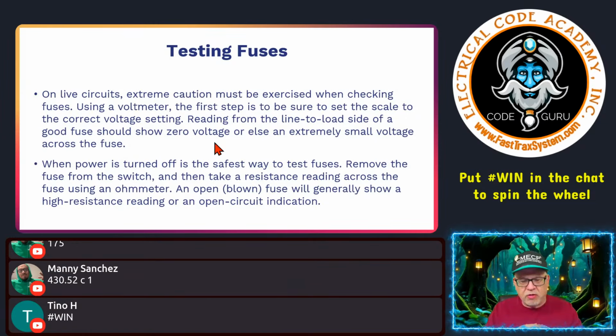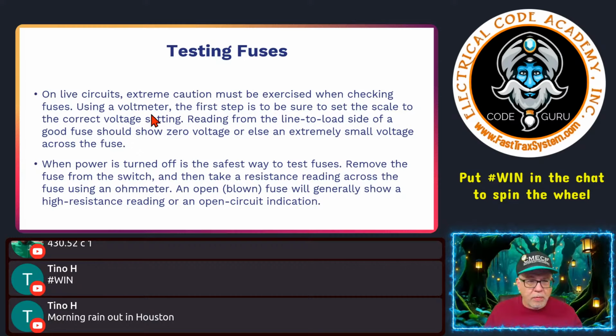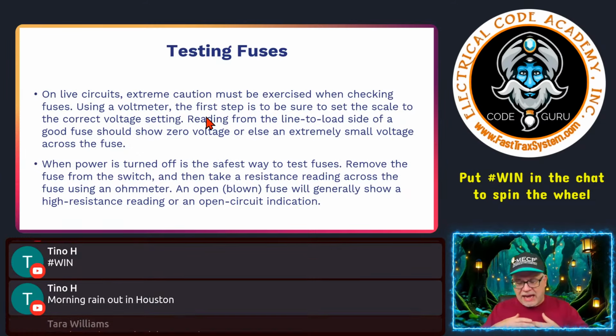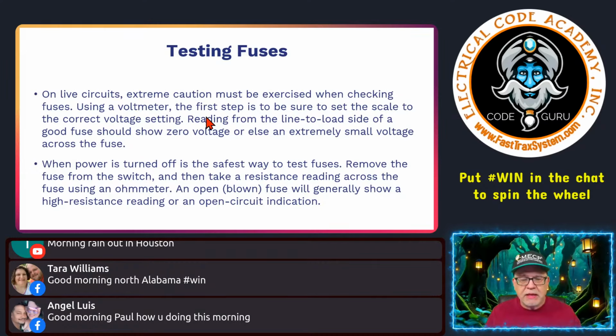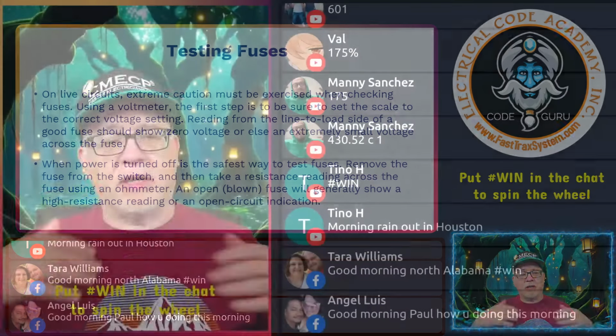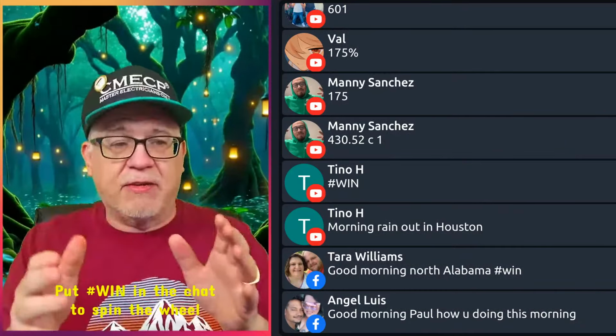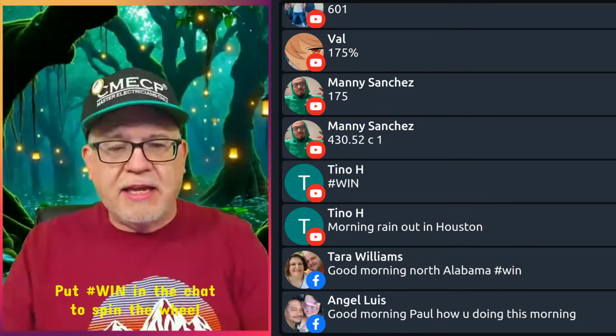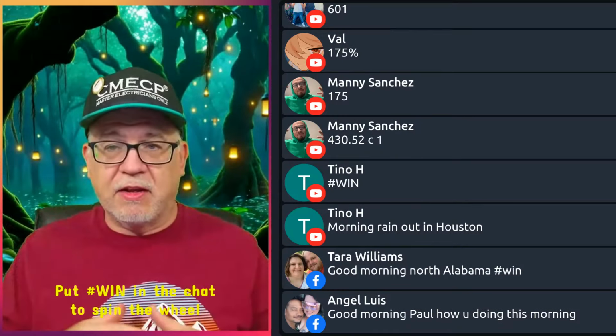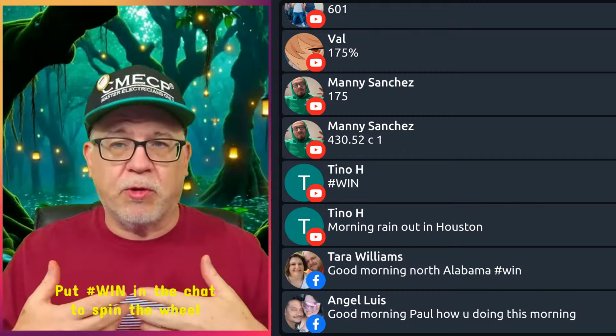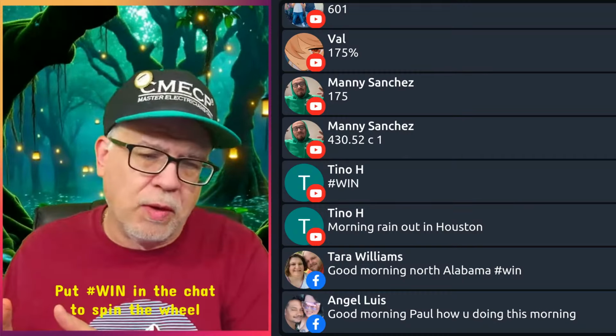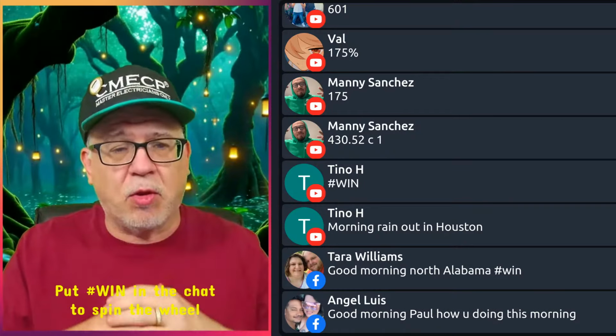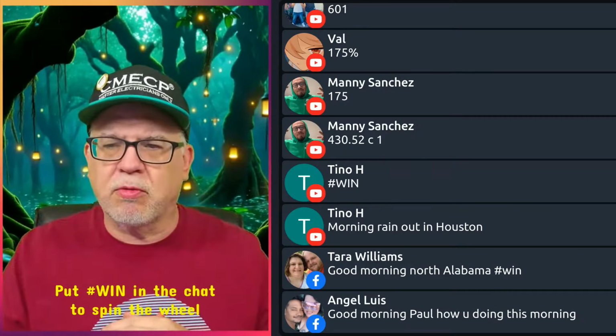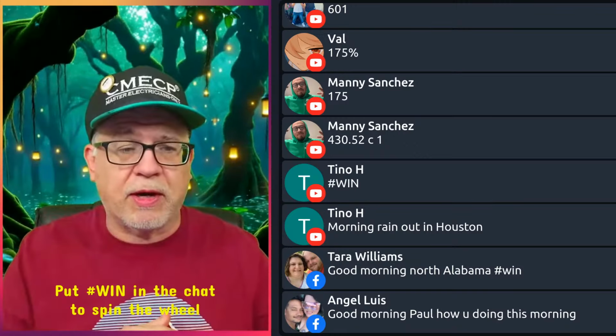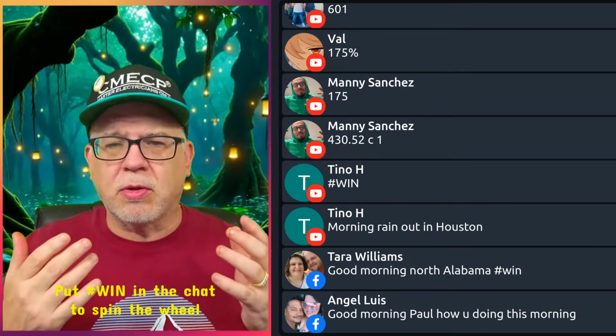Now, when power is turned off is the safest way to test. Now, this is another thing right here. People ask, for example, about working clearances at disconnects for HVAC equipment. I get this question all the time. They ask me, do I need working clearance at an outdoor HVAC equipment disconnect for the condenser? And the answer to that is yes. It has to have working clearance because chances are that is the place that you're going to be going if you're a technician checking before you start digging into the equipment. You're going to be right there making sure that you have the line voltage, that the fuses are okay, that everything's passing through fine, that you've got the right level of voltage, you didn't lose a leg anywhere. That's where you're going to be doing it because that's the easiest place to do it first.